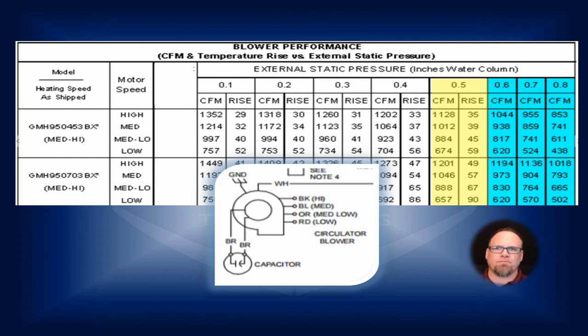Now think about this. Okay, I'm going to switch gears and I'm going to tell you something, and it's going to correlate to heating, and I think you'll get it. Right? This is how critical it is that we set these up. In the past, some of the older furnaces that we put in had an air temperature rise nearly 100 degrees. Okay, now you take the same BTU value in today's furnaces, our air temperature rise, according to many of the efficiency tests and setup charts, they want you to be somewhere around the 50 degree temperature rise setting.